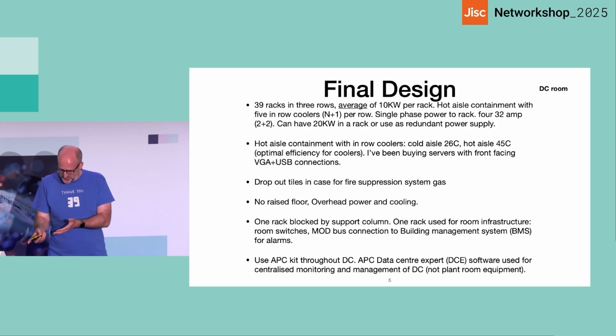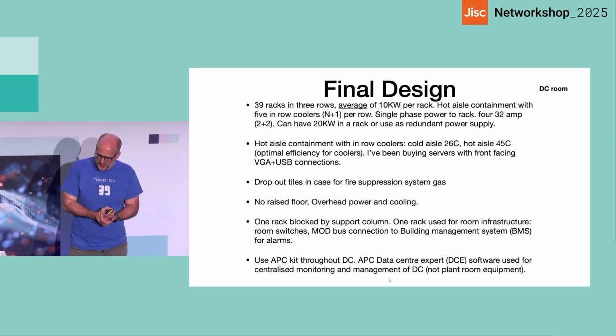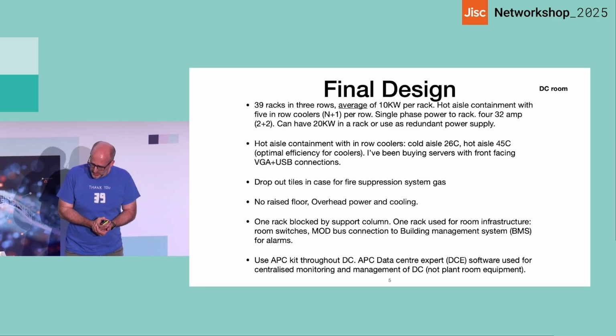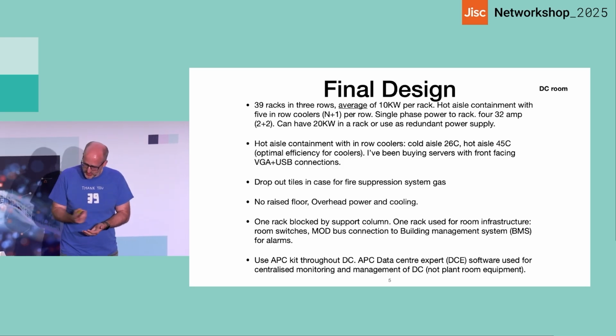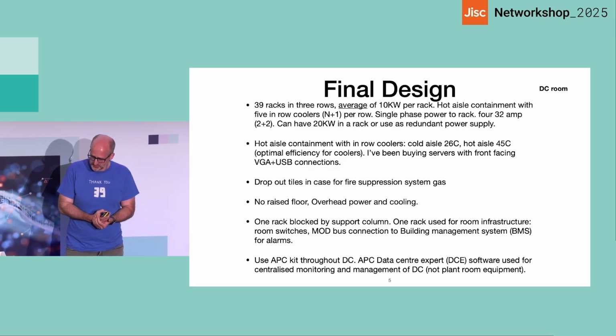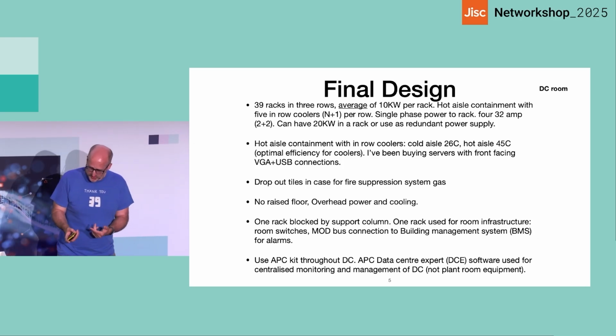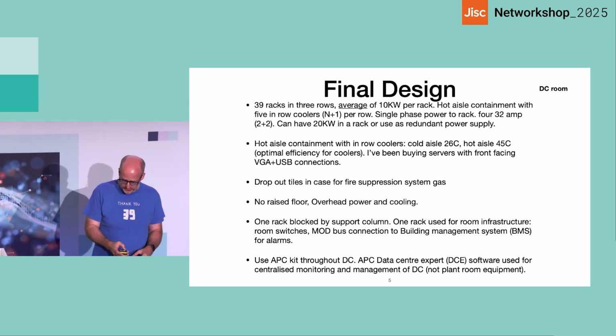We do not have a raised floor in this room, so all the power and cooling has to come from overhead. That's basically a cost thing. We couldn't really afford to build a raised floor, and actually the space in the room doesn't allow for it as well. You'll see some pictures and you'll see some columns that get in the way and so on. That's just annoying. We connect to the building management system in parts with Modbus. And in the end solution, we were using APC hardware throughout, and we're using the Data Center Expert to monitor the room inside the room.